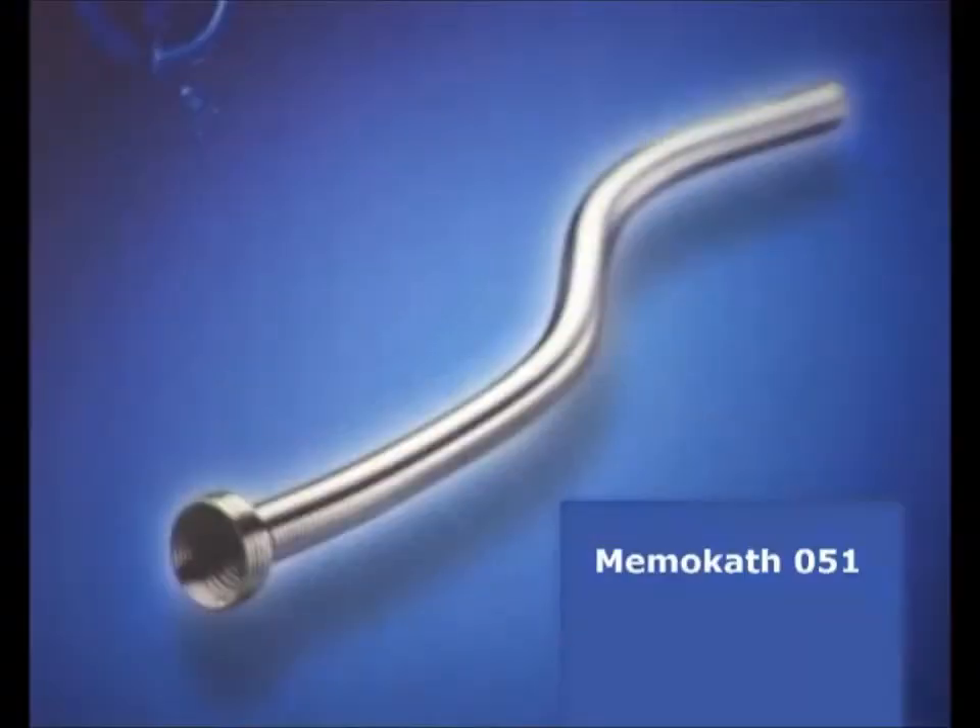The Memokath 051 is a thermo-expandable titanium nickel alloy spiral developed for long-term urethral stenting. It has a unique temperature-activated shape memory which makes it adapt itself to the host tissue. These properties make it easy to remove obstructed or migrated stents.